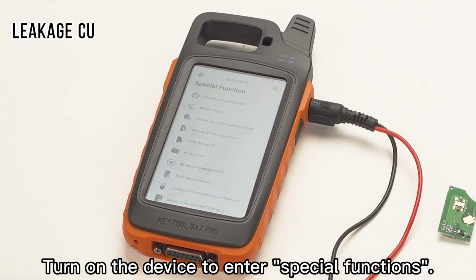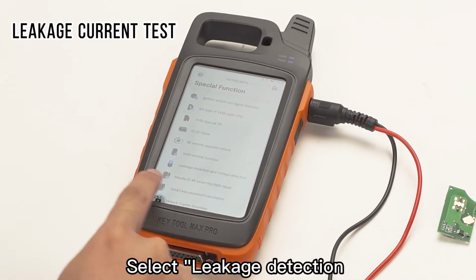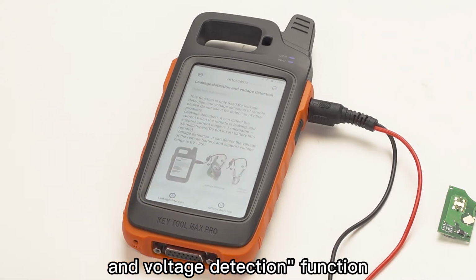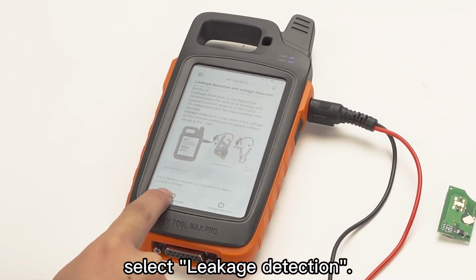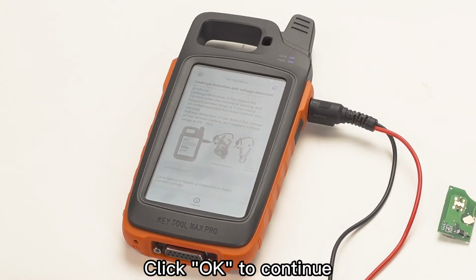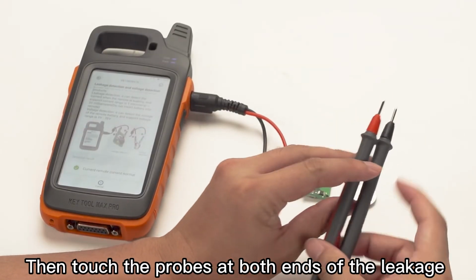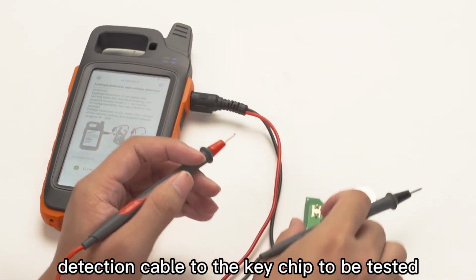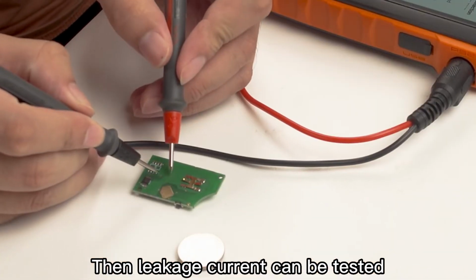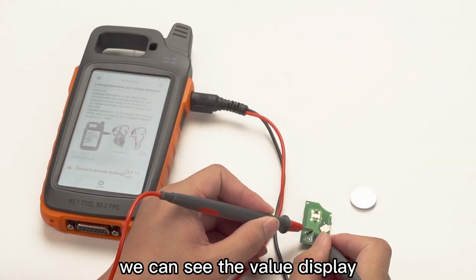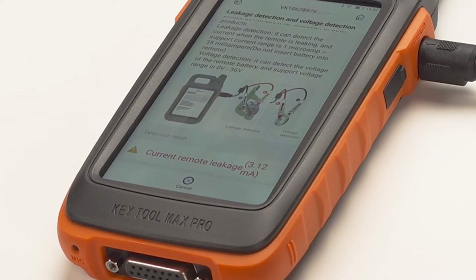Turn on the device to enter Special Functions. Select Leakage Detection and Voltage Detection function. After entering, select Leakage Detection. Click OK to continue. Then touch the probes at both ends of the leakage detection cable to the key chip to be tested. Then the leakage current can be tested. On the device screen, we can see the value displayed.